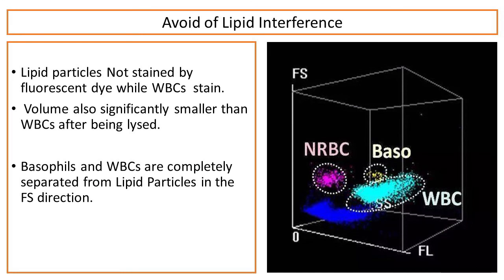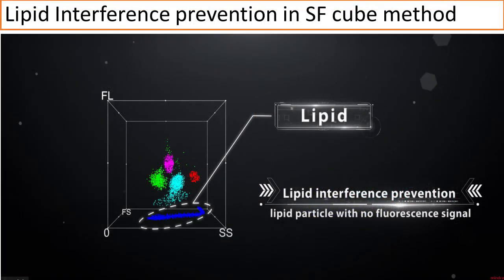To avoid lipid interference in this method: lipid particles are not stained by fluorescent dye, while WBCs are stained. The volume of lipid particles is significantly smaller than WBCs. After being lysed, basophils and WBCs are completely separated from lipid particles in the forward scatter direction, thus preventing interference and ensuring more accurate WBC results.